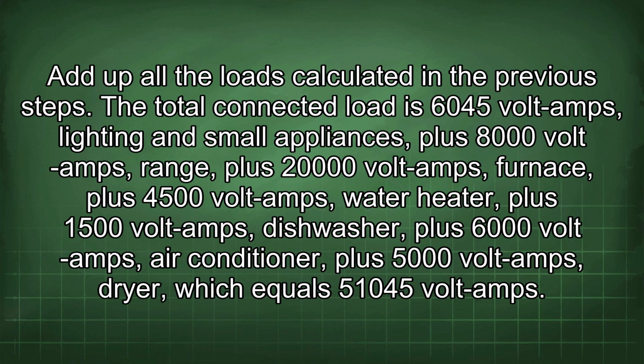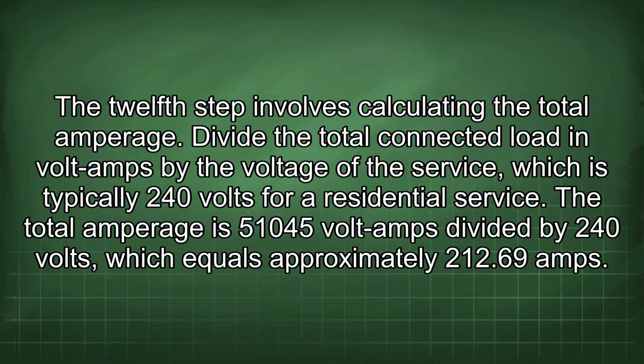Add up all the loads calculated in the previous steps. The total connected load is 6,045 volt amps, lighting and small appliances, plus 8,000 volt amps, range, plus 20,000 volt amps, furnace, plus 4,500 volt amps, water heater, plus 1,500 volt amps, dishwasher, plus 6,000 volt amps, air conditioner, plus 5,000 volt amps, dryer, which equals 51,045 volt amps. The 12th step involves calculating the total amperage. Divide the total connected load in volt amps by the voltage of the service, which is typically 240 volts for a residential service. The total amperage is 51,045 volt amps divided by 240 volts, which equals approximately 212.69 amps.